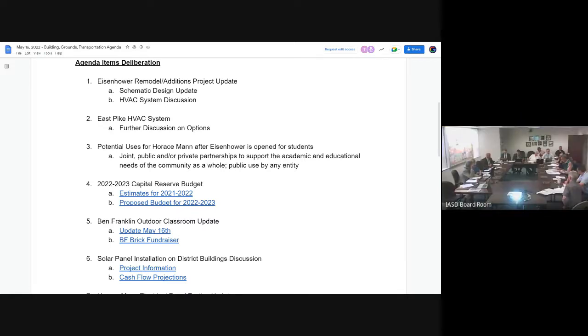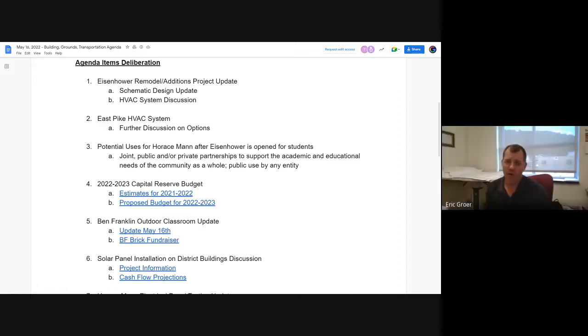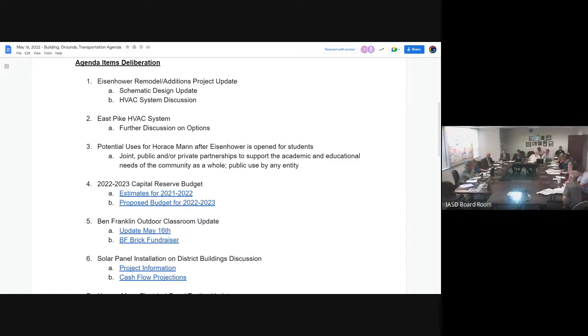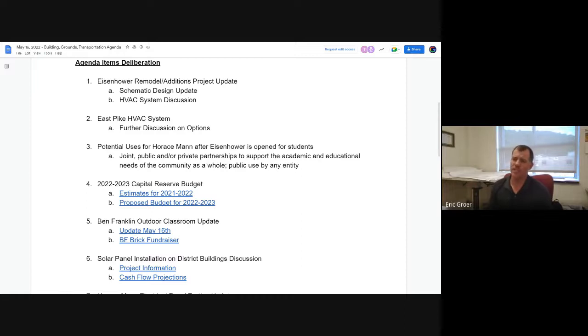Why is it so high? The energy costs? Yeah. Well, the reason you're not seeing great energy costs with geothermal is the fact that the school is going to be closed during the summertime. So, when you have a geothermal system that doesn't replenish the well field in the summertime, when the school needs cooling, you have an unbalanced load. That's kind of the nature of K through 12 schools, and that's why I typically don't see geothermal being used in K through 12 applications.